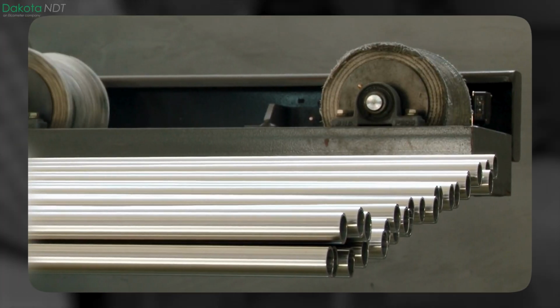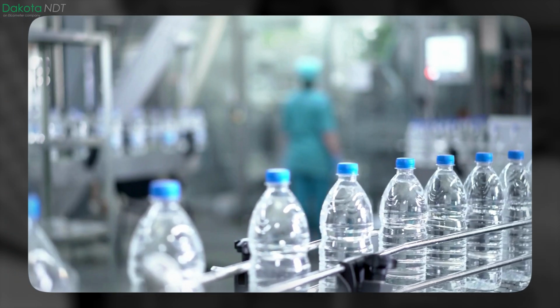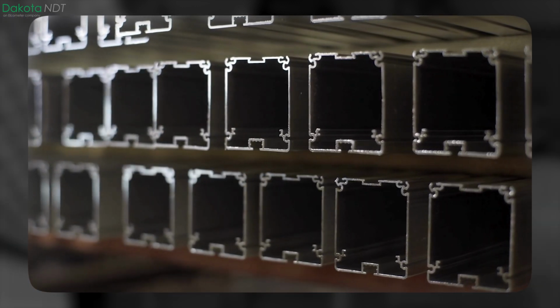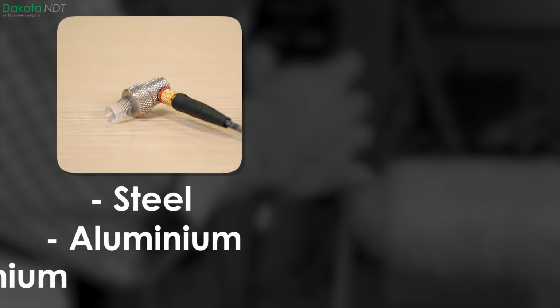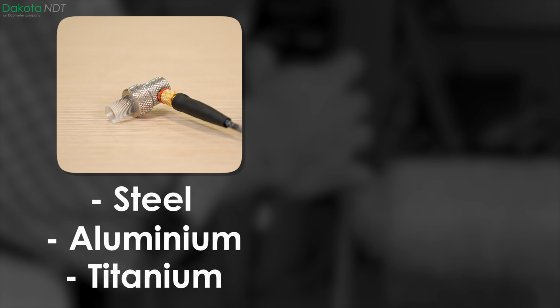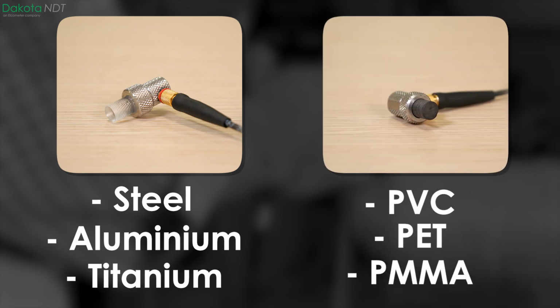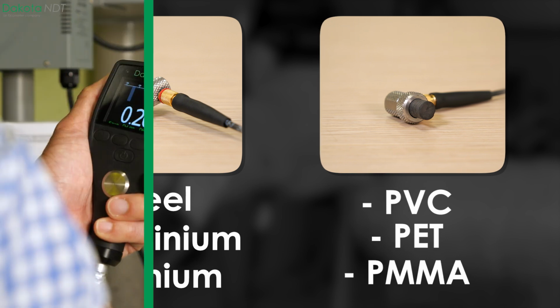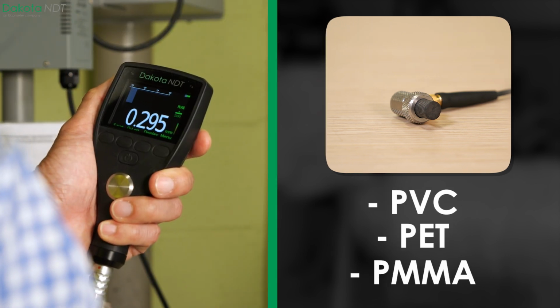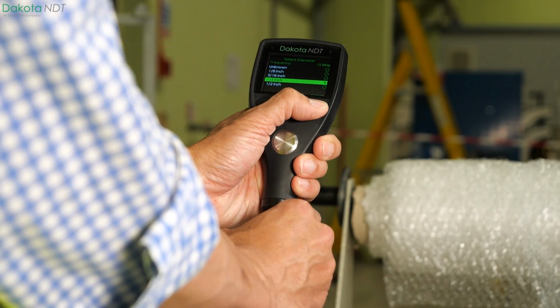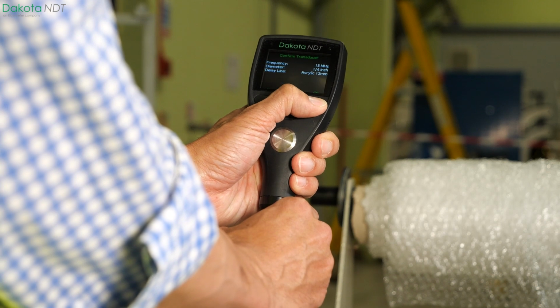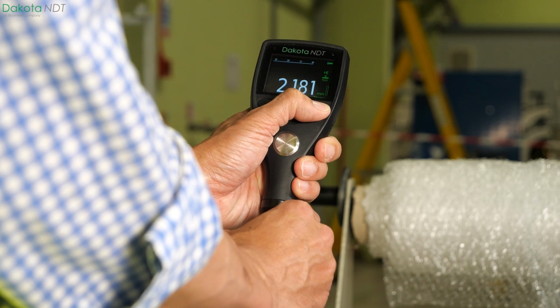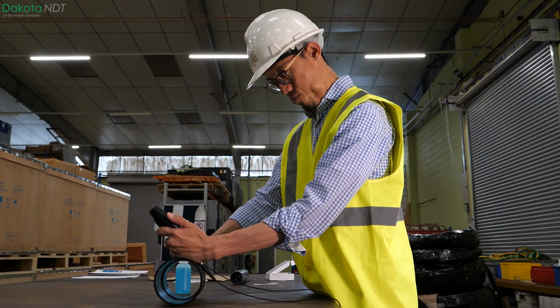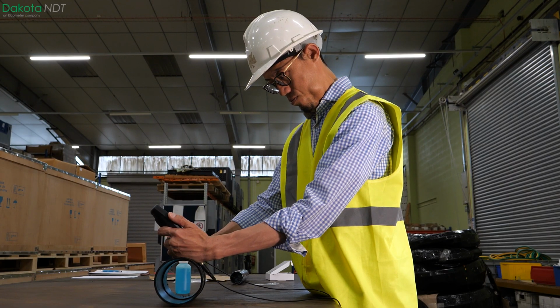The material you are measuring will affect the material of the delay line you should use. For example, acrylic delay lines are suitable for measuring on steel, aluminium, and titanium, while thin plastics and other similar materials should be measured using a graphite delay line, with the gauge set to plastic mode. You simply input the length and material of the delay line before starting, and the gauge will subtract it from future measurements, leaving just the thickness of the material.